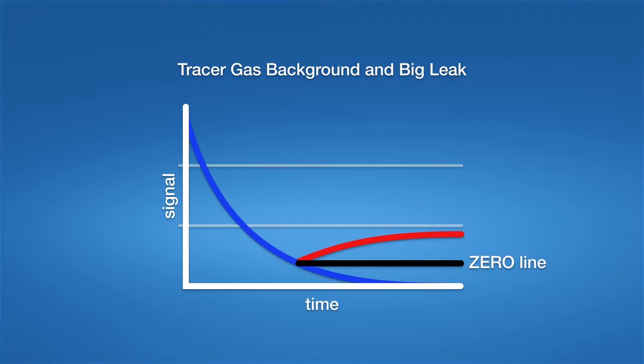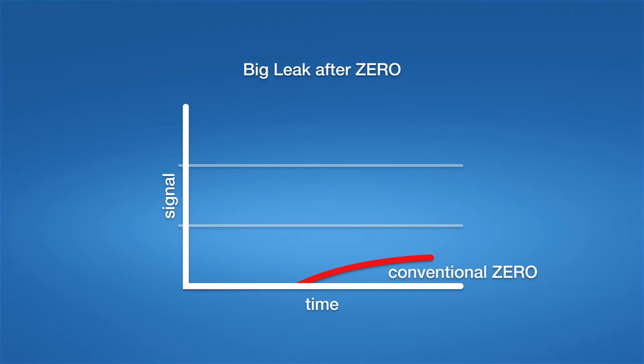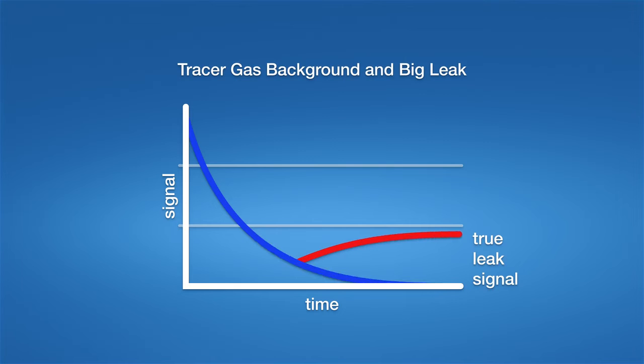With the conventional zero functions available in the industry, only the signal above the black zero line can be shown on the leak detector as leak rate. Then it will look like this, but we know that the real leak size is bigger than that. The real leak size is the difference between the blue curve and the red curve.